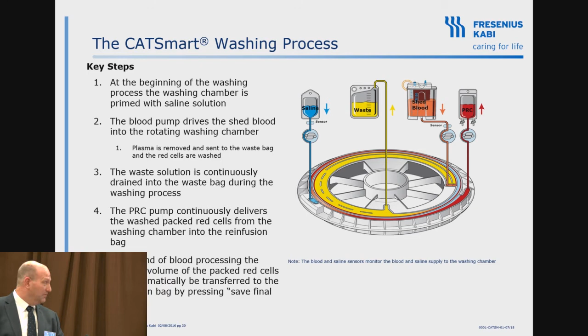How do the red cells move through this chamber and get pulled out to be a wash-packed red cell? Again, a schematic here, 4 tubes, 3 of them having pumps. The waste tube does not. Blood comes in from the reservoir. The one thing you have to remember, we're looking at centrifugal force. Everybody uses centrifugal force to separate the blood into its components. So as the blood comes in on the inner area and then immediately separates, it's kind of like those tilt-a-wheel rides, all the people going flying out. Same thing. And then saline is being pumped in at the same time, and then the waste is coming out as we're pulling in more and more red cells and pumping out plasma, and then the PRC comes out at the very outer end at the highest centrifugal force area.